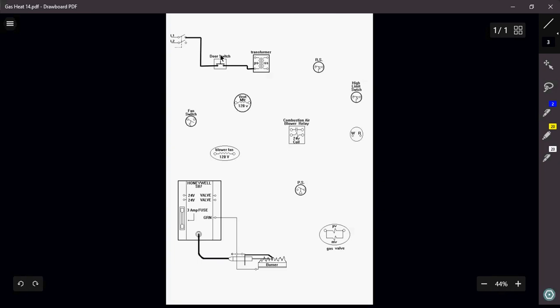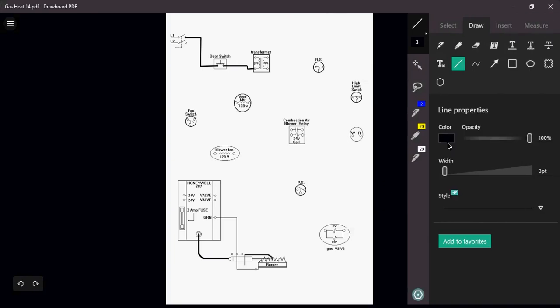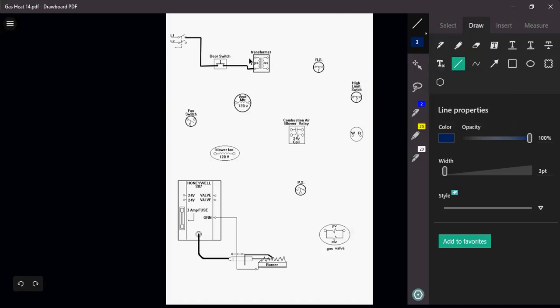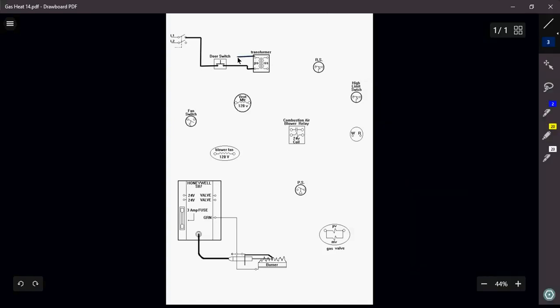So that door switch right there is our control device for our transformer. If that door switch is open, I kill my power to my transformer. So that's where I say it's a safety. We don't want anything bad to happen when somebody is working on it that maybe is not qualified for it. Okay, so I'm going to complete that circuit. I'm going to use a nice color blue here. That blue out of my transformer, I'm just going to come straight back out.